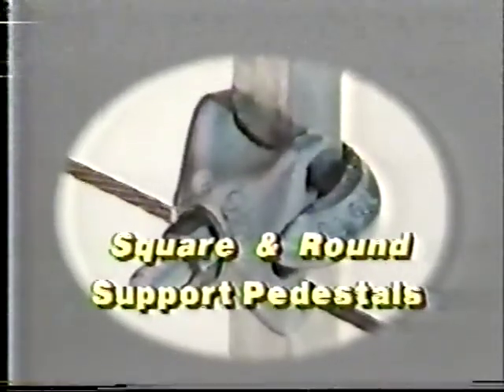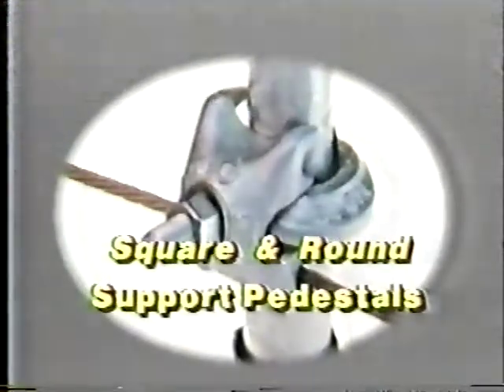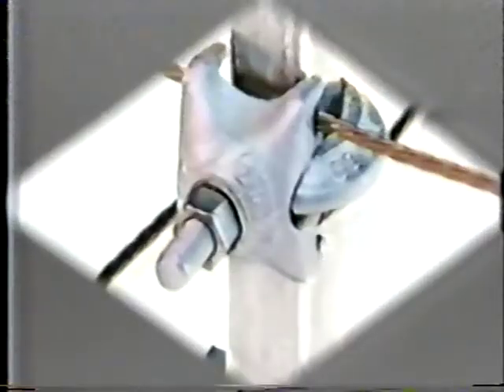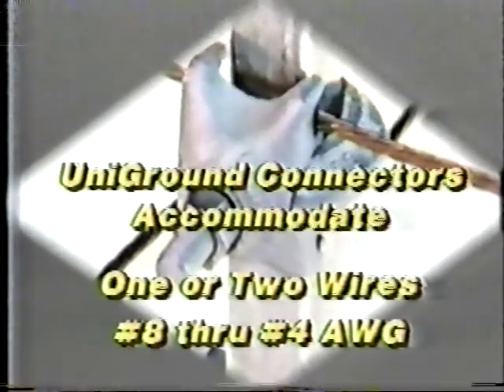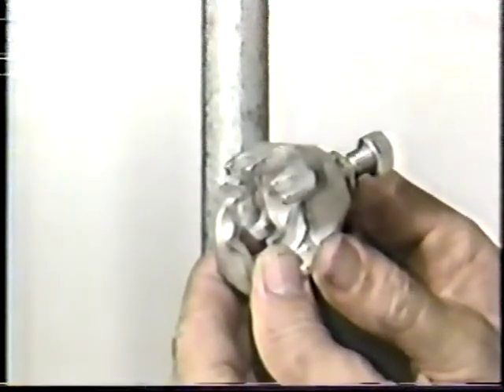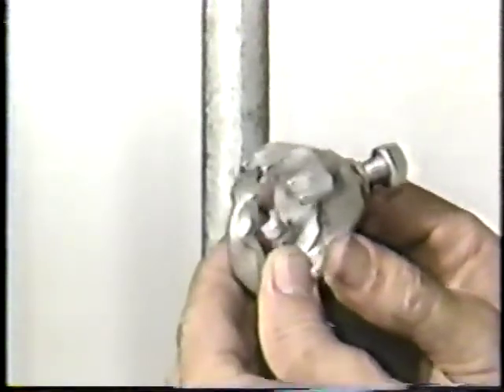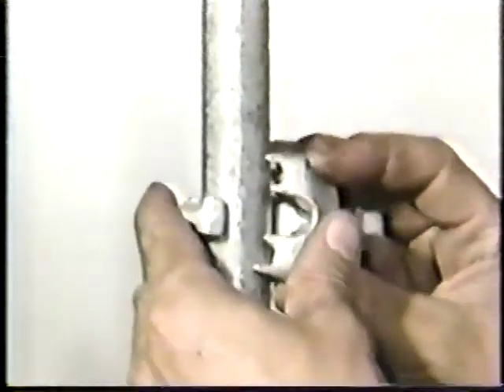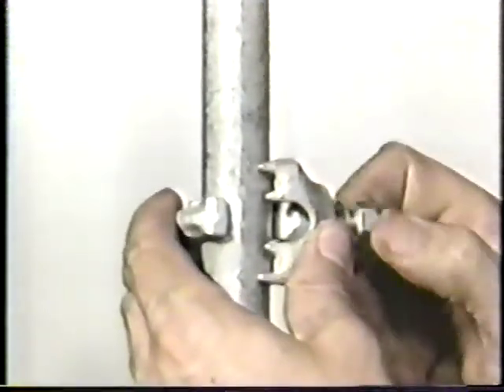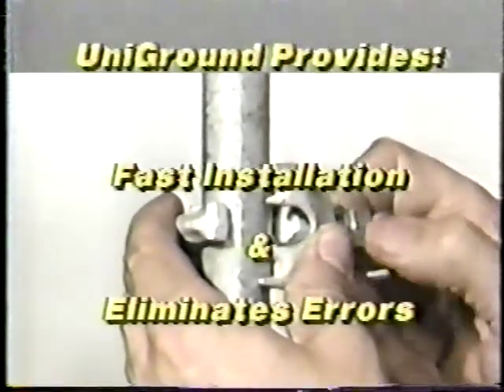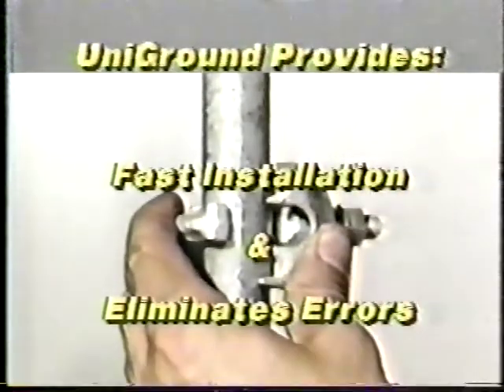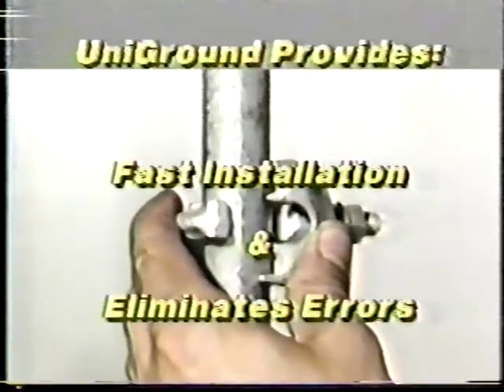Burndy's Uniground connectors can be used on both square and round support pedestals. And since they'll accommodate 1 or 2 wires ranging from number 8 through number 4 gauge, they clearly provide a universal solution for the specification writer. Because Uniground is a single bolt design, there's no need for disassembling the connector for installation. This permits a high-speed installation and eliminates possible errors in tightening multiple screws.